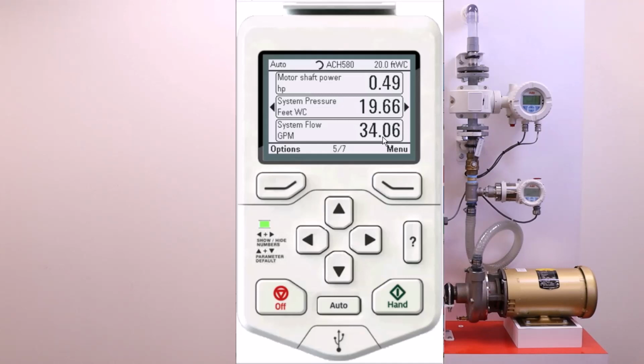And we see here the system is getting itself up to a little bit over 20 feet of water column. It's starting to stabilize. I can look at the next screen over that I had set up. And there we are. Output frequency 58 hertz. System pressure is about 21 feet of water column. If I back up, it's at 21 feet of water column.